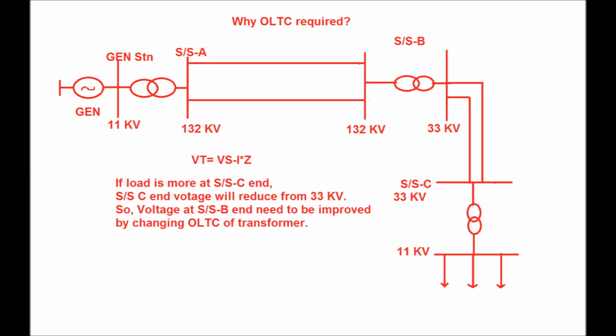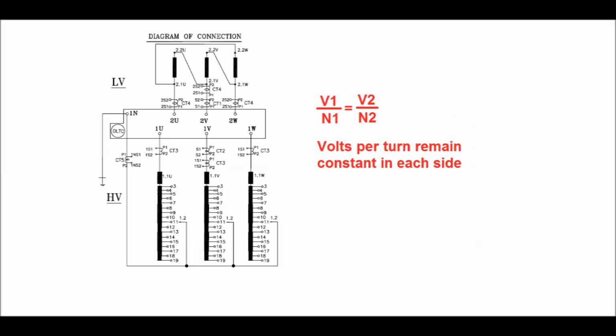So by means of tap changing in online mode, that 33 kV voltage can be increased up to 35 kV, so that at the distribution end the 33 kV voltage is retained. This is how tap changing helps to regain the voltage profile at the distribution substation. Normally the tap winding is provided in the HV side winding in order to handle a lesser amount of current.